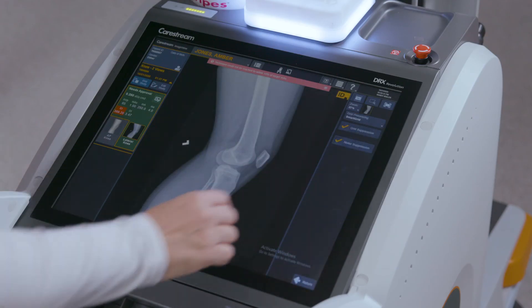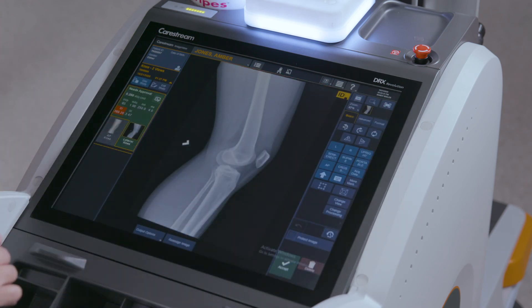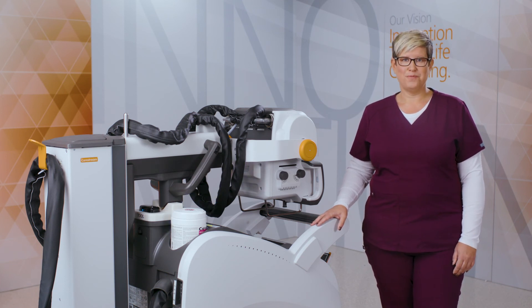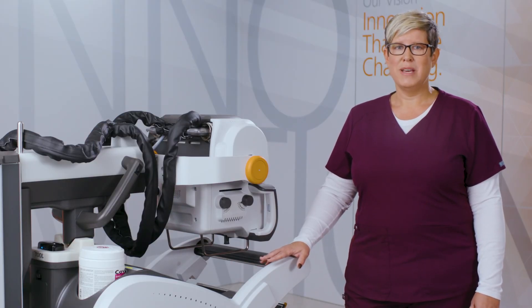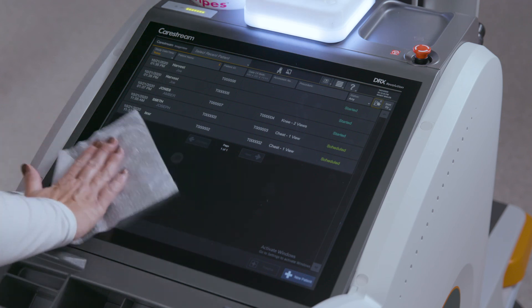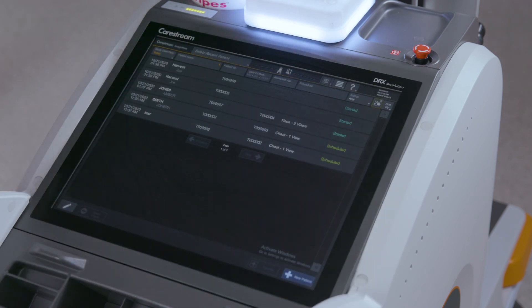Smart Grid gives image quality similar to that of a grid without the actual use of a grid. This both increases comfort to patients and decreases workload to techs. Better yet, Smart Grid can be applied either before or after an exposure. Special pediatric software gives superb image quality based on size and weight of the patient. Both the main monitor and the tube head display are flush mounted for easy cleaning and increased protection against dust and liquid ingress.